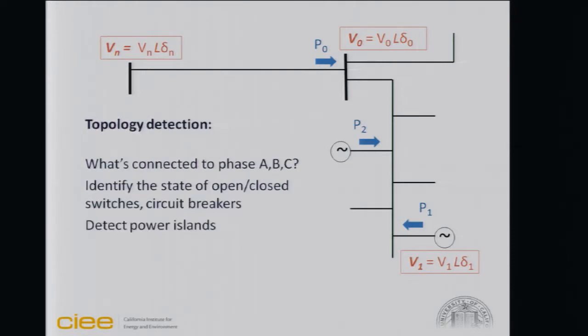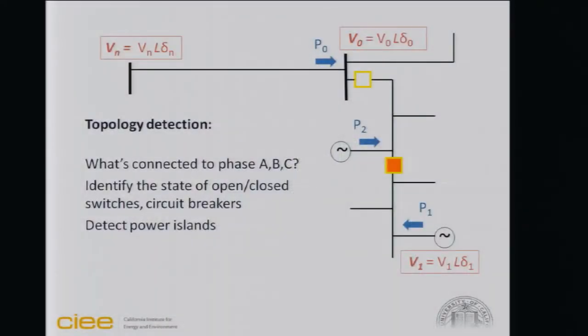Topology detection is of real practical importance to utilities, because they don't always know they can trust the status of switches being open or closed at different points. Actually starting with phase identification, many utilities aren't really sure what's hooked up to phase A, B, or C. So those are algorithms we're working on, interpreting the kinds of measurements I showed you to see if it's plausible for voltages and currents on phases A, B, and C to be aligned, or whether they're mislabeled or misaligned.